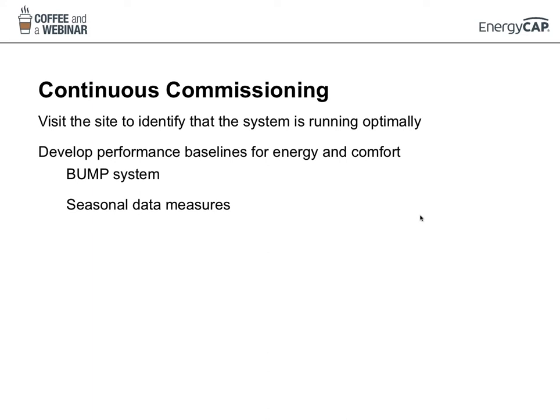For us, we have building utility management panels. In our district energy system, we put little notes on these BUMPS system panels to tell us what our seasonal data measures are. So if we see the kilowatt-hours at 3 o'clock are above our baseline, we might look into it and ask what's happening. Same with chill water, same with steam. We have note cards on these panels giving us the time frame and amount of energy that should be used for that season.